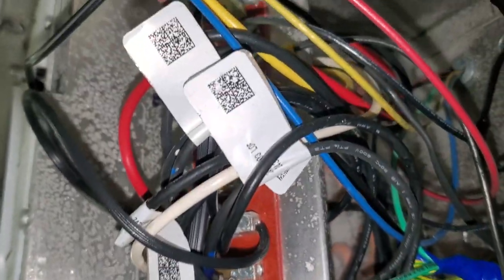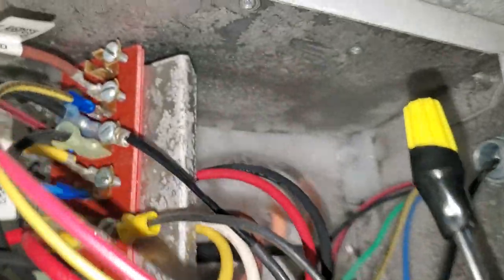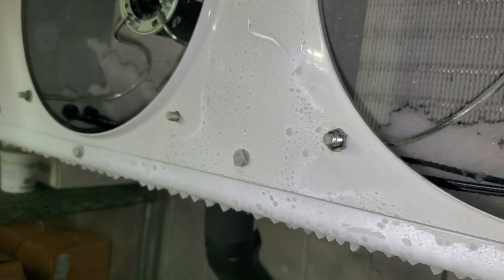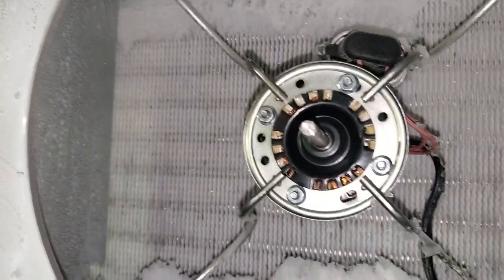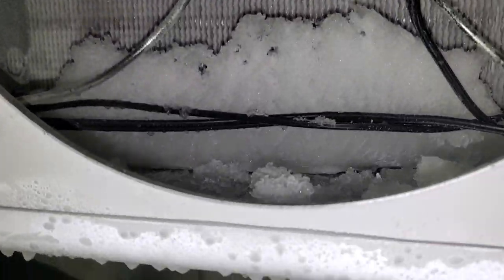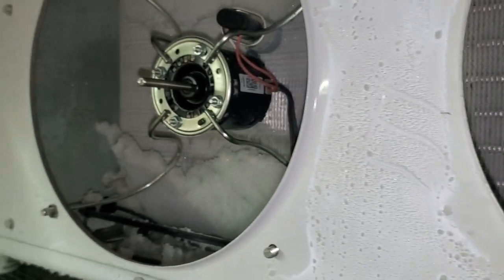This is really bizarre. I don't see any direct shorts. I don't see any burn marks. The only thing I saw was that compressor contactor outside. I don't like this. Don't see any issues with the motor. That vibration — I'm still concerned about that. We'll have to look at that blade when we put it all back together. It's possible ice has been falling on it or something.